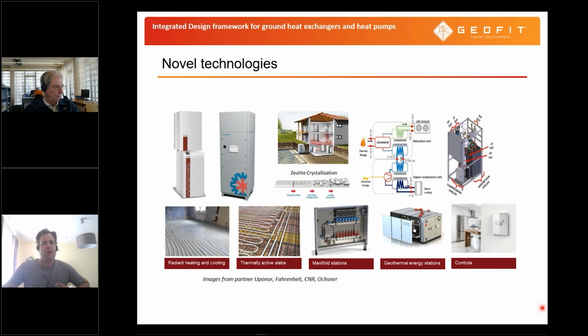So we have this electrical driven heat pump, which is a compression heat pump, and the innovation here is the refrigerant. So we use a medium to low GWP, that's the global warming potential, refrigerant to provide the heating, and the thermally driven heat pump, or also called hybrid heat pump.